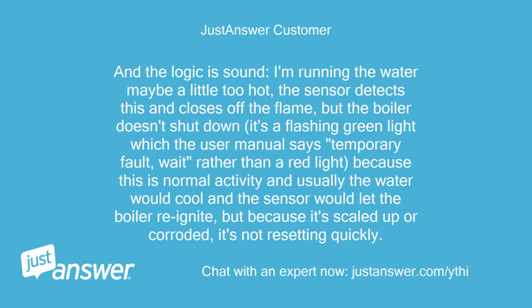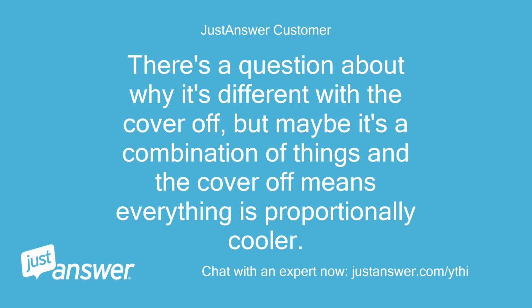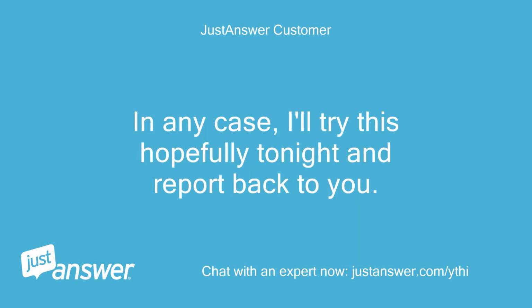And the logic is sound. I'm running the water maybe a little too hot. The sensor detects this and closes off the flame, but the boiler doesn't shut down. It's a flashing green light which the user manual says temporary fault, wait, rather than a red light, because this is normal activity and usually the water would cool and the sensor would let the boiler reignite, but because it's scaled up or corroded, it's not resetting quickly. There's a question about why it's different with the cover off, but maybe it's a combination of things and the cover off means everything is proportionally cooler. In any case, I'll try this hopefully tonight and report back to you.